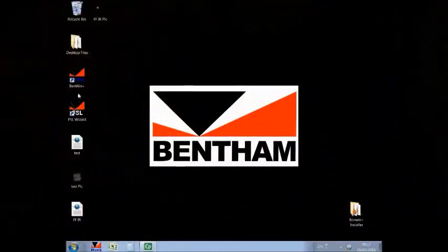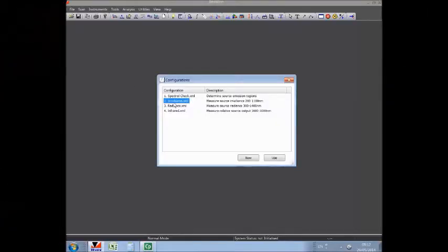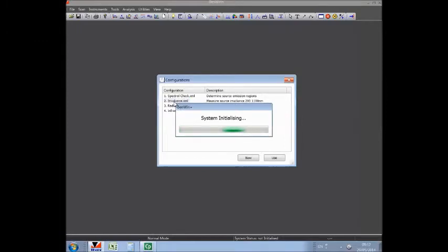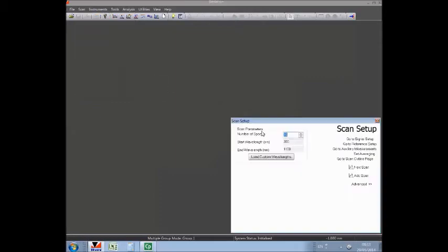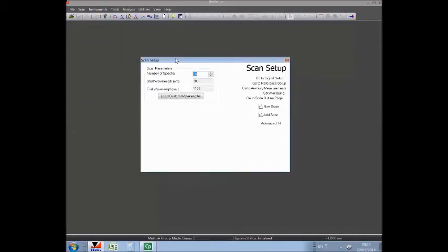We will now turn to BenWin+ and initialize in the irradiance configuration. Where the fibre bundle hasn't been installed, we should wait to the end of this procedure. We will hear the motor stop moving and this initialization window will go away before we fit the fibre bundle, and now we can do so with no fear that it will impede the movement of the slits. We go to Scan Setup for this CL6 calibration measurement.